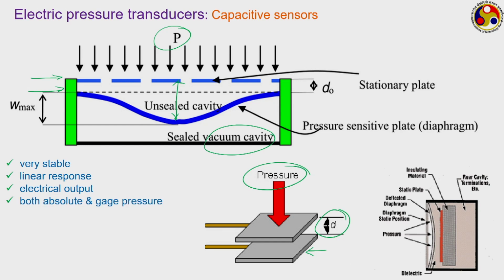Both absolute and gauge pressures we can get, like the situation shown in these two particular situations. If we go back to the first diagram, here we have a vacuum cavity. So, what pressure can it measure? It gives you the absolute pressure. Whereas, instead of maintaining a vacuum, if we maintain a fixed reference pressure there, generally the atmospheric pressure, then we can get a gauge pressure reading from this. So, it can give you both kinds of measurements.